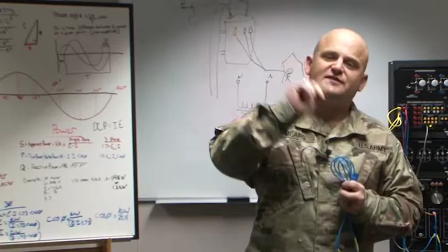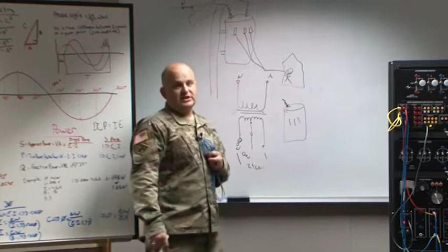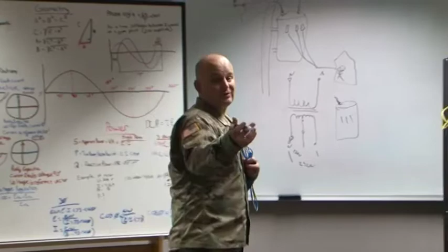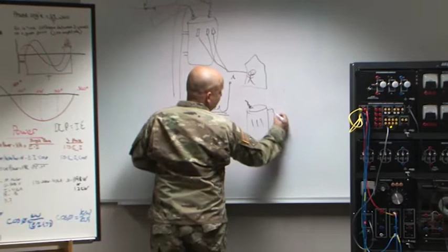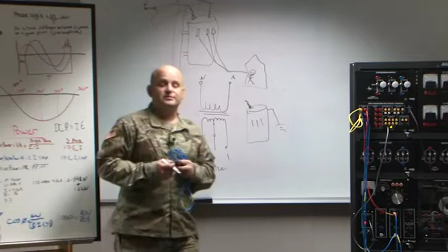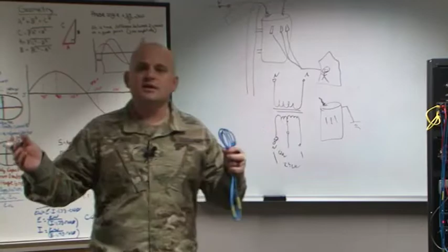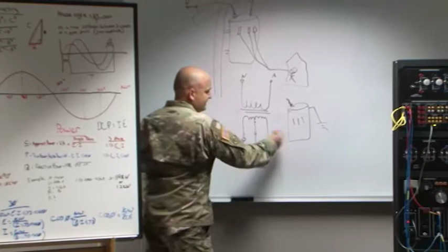Also, on distribution transformers, you're going to see some common ones. I drew it like this, but especially on the pole-mounted electric transformers, you're only going to see one of those H paddles. The reason is H2 is bonded to the case, which is bonded to the ground going down the pole to a pole ground. So really, this is coming off down through the pole. This is a good indicator to you, just by seeing that you've got a phase-to-ground connection there, a voltage reference that you're using to put power to that transformer, but you're still getting multiple voltages out of the secondary side.